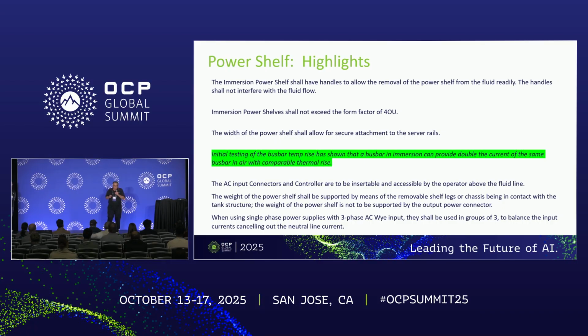When using single-phase input supplies, or with 3-phase Y input, these should be in groups of 3. The idea is that in a Y configuration they're balanced, so you don't get neutral currents. This is what OCP has done in rack power to date with single-phase power supplies, and we wanted to keep doing the same thing. It makes sense—that way the neutral line isn't carrying a lot of current, and you don't have problems.